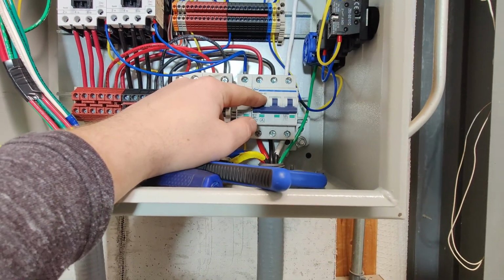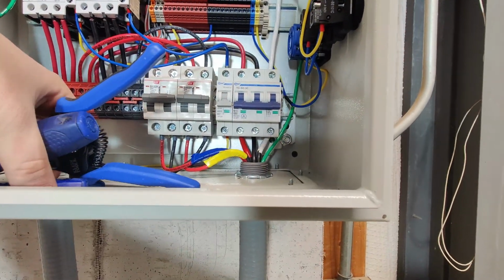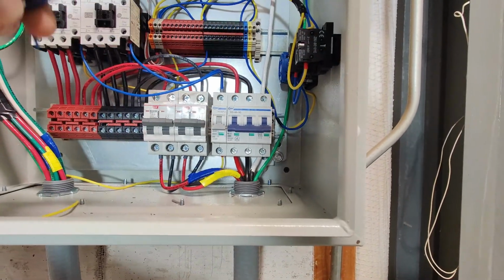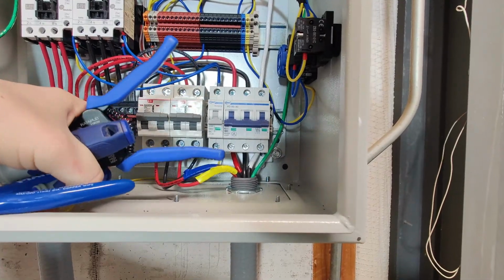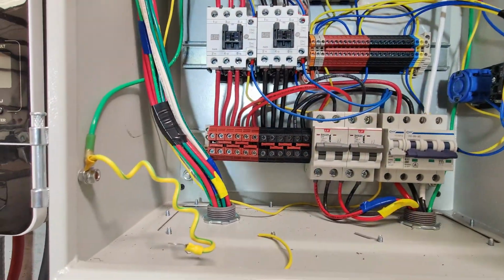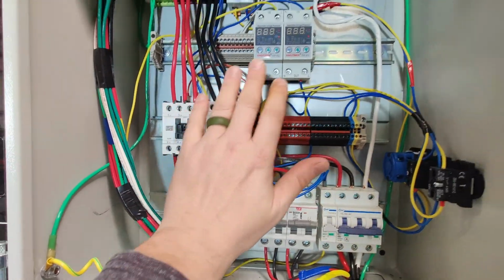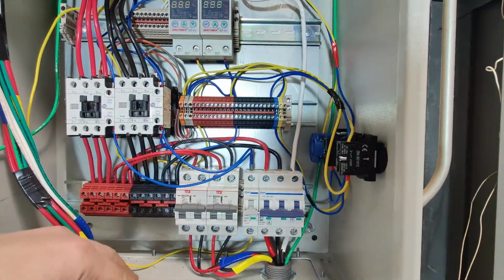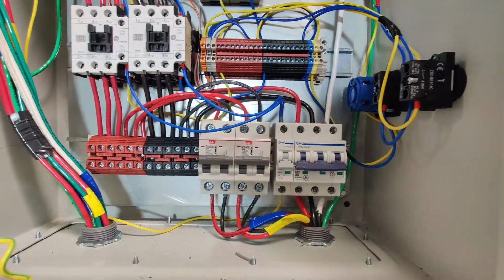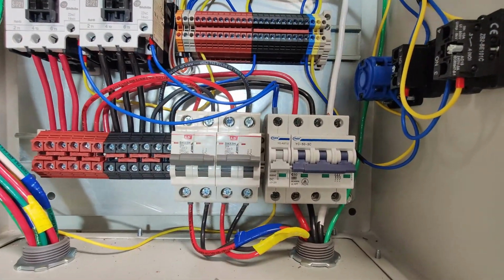This shunt trip breaker is always going to be in a trip state unless the system is activated. And what this allows us to do is have one simple step instead of operating a third contactor. That's how it was before: once these two were active, when these turned on, it would activate a third contactor. What this shunt trip breaker allows us to do is essentially have a one-time reset.